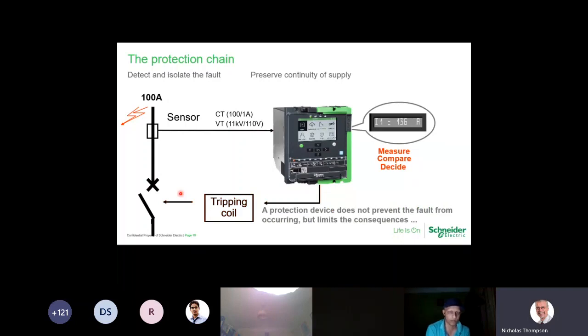If it decides that the fault is a permanent fault and is there for longer than what we've programmed the relay to allow for it to actually work, then hey ho, it will set in motion a chain where it will send a supply or a trip signal to the tripping coil, which will then open the circuit breaker, and provided everything is in good working order, and this is where maintenance comes in, the circuit breaker should then open.